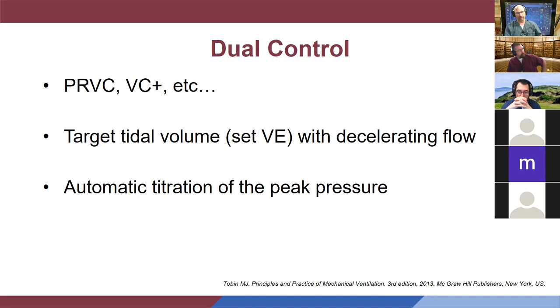And the clue to this is your airway total pressure. Instead of being, say, around 40, it's going to be down around 10. It's usually 5 above your PEEP level. So if your PEEP's at 10, the total airway pressure will be 15. When you start seeing your numbers reduce like that, and you look at the patient, they don't look normal, their work of breathing's up, then that's when you need to switch over to the mode.